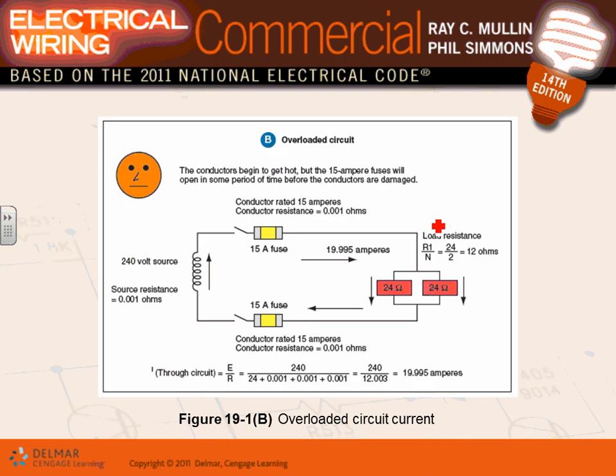Let's go to the overload condition. Now, I went to Adam, and Adam decided to put two microwaves. Here's microwave number 1. This is microwave number 2. He decided to plug another microwave from the same circuit. Look what happened. Now I have two loads in parallel. You guys remember, when you did two resistors in parallel, what happened? You cut their impedance by half, right? They're the same, so you cut the impedance by half. So the impedance here becomes 12 instead of 24.